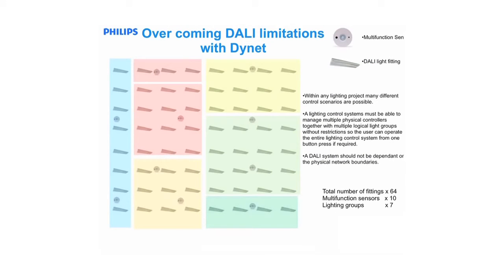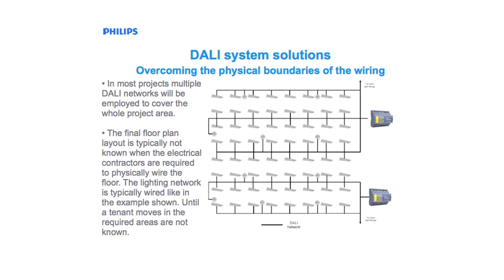Applying a control solution into a real project example can be challenging if the lighting control does not allow for the coordination of multiple DALI universes together. Very rarely will one DALI universe fill the needs of an entire floor. Typically, multiple DALI universes need to be used in conjunction to cover the full scope of a project.